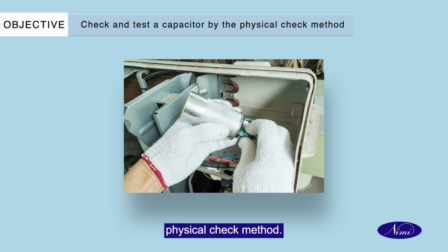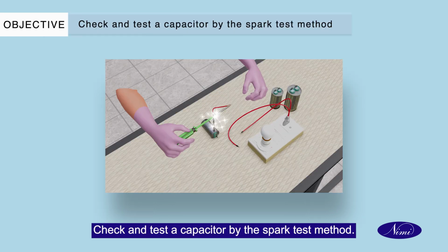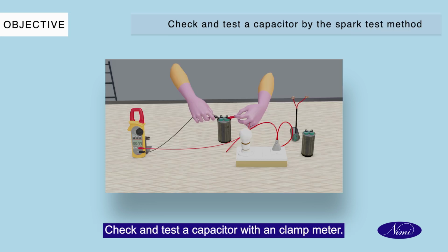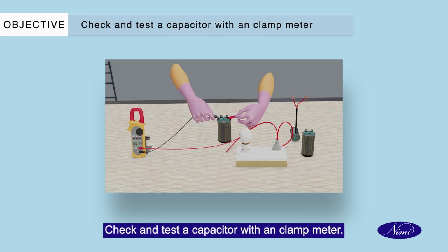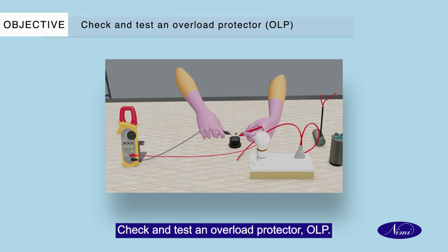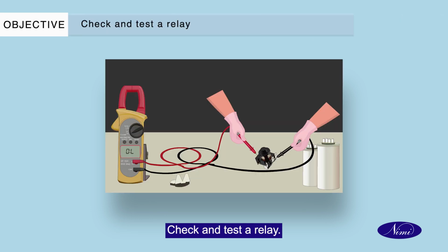physical check method. Check and test a capacitor by the spark test method. Check and test a capacitor with a clamp meter. Check and test an overload protector OLP. Check and test a relay.